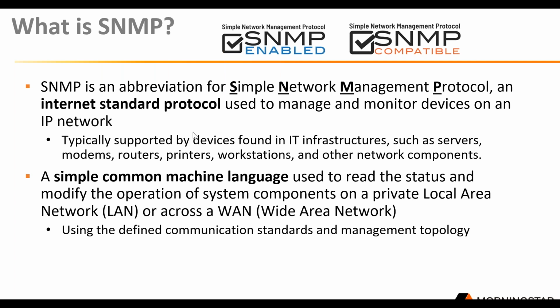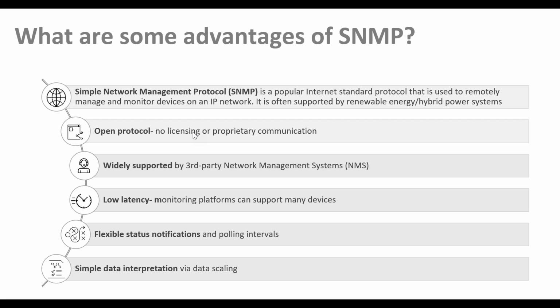So with that said, let me talk about some of the advantages of SNMP. One of the key things is it is an open protocol. So there is no licensing or proprietary communication that you need to adopt or go through an approval process in order to implement or pay for. It's all free licensing. Anybody can use it. We have implemented SNMP version 2C. There are several variants of SNMP dating back to the 1980s.